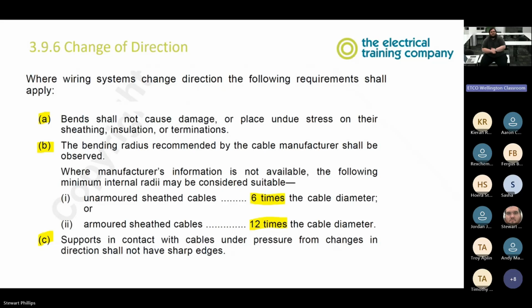Anyway, cool. So the bending radius recommended by the cable manufacturer shall be observed. When the information is not available, a good consideration is 6 for unarmored sheath cables. So your normal cables, 6 times the cable diameter is the internal radii of the bend, or for armored sheath cables, so your steel wire armor, 12 times the cable diameter. This way we ensure that it's a nice smooth bend and it's not going to cause undue stress to the copper sheathing, or in the armored case, the armor.